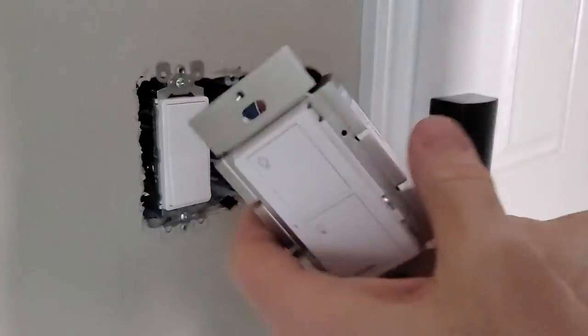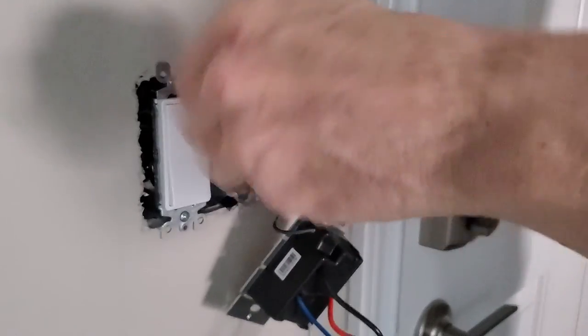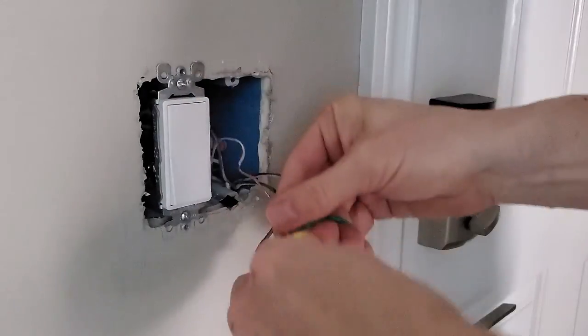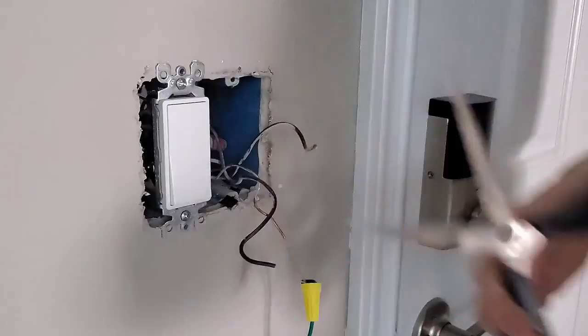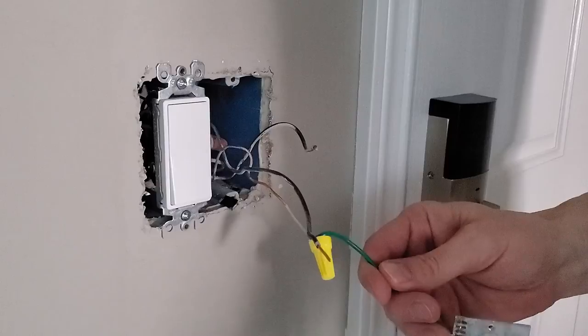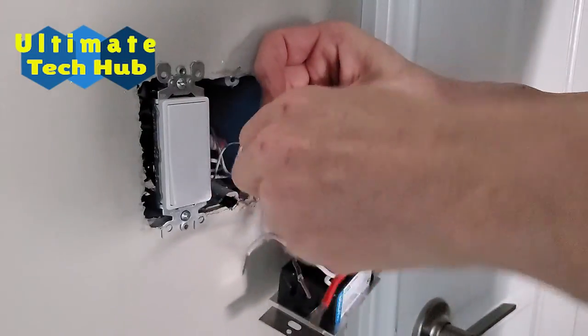Here's the new switch and some wire caps. Start by connecting the green wire to the copper ground wire using a wire cap. Next, strip back the two black wires about half an inch. Connect the black wire from the new switch to one of the black wires from the wall box, and connect the red wire from the new switch to the other black wire from the wall box. Note: both of the loaded hot wires are black in my wall box.